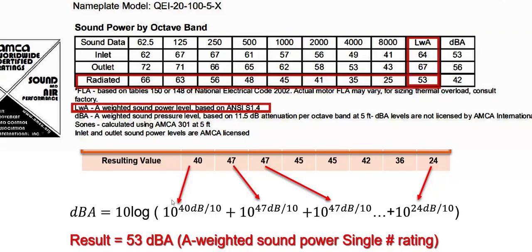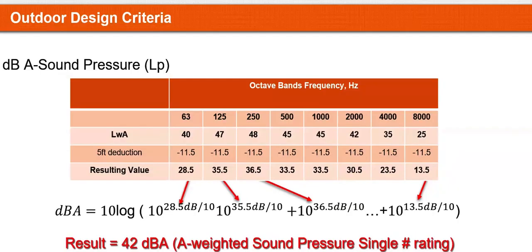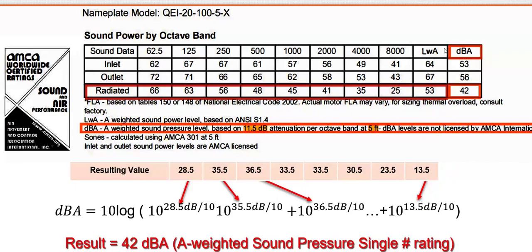These eight numbers get quantified in a single number rating, which means this unit, when you plug it in, is radiating airborne noise at 53 decibels. Now, the second number that you see to the right on any cut sheet for equipment is pressure, whereas LW is power. The dBA that you see on the right is pressure. We hear pressure. The human ear, as a sound wave, expresses on your eardrum, that pressure is force over area to move your eardrum back and forth. What we hear is pressure. What you measure with a microphone is pressure.